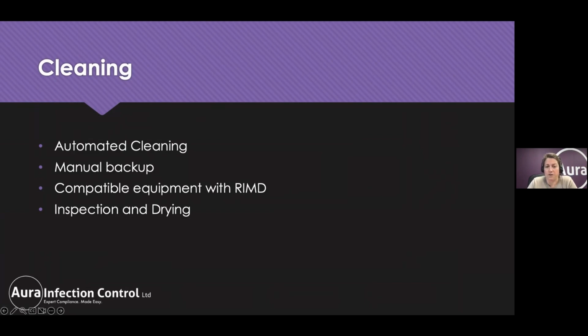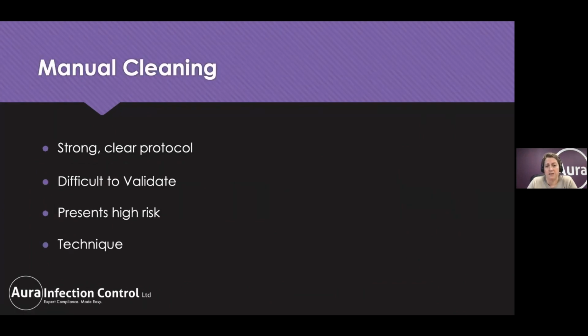Now, we have some options for our cleaning. We can use manual cleaning, we can use an ultrasonic bath, or we can use an automated cleaning process in a washer disinfector. Whichever process you choose, it needs to be compatible with your device, and the decon lead should be involved in the procurement of the instruments and the devices to make sure that you're not buying something that can't be processed with your current methods.